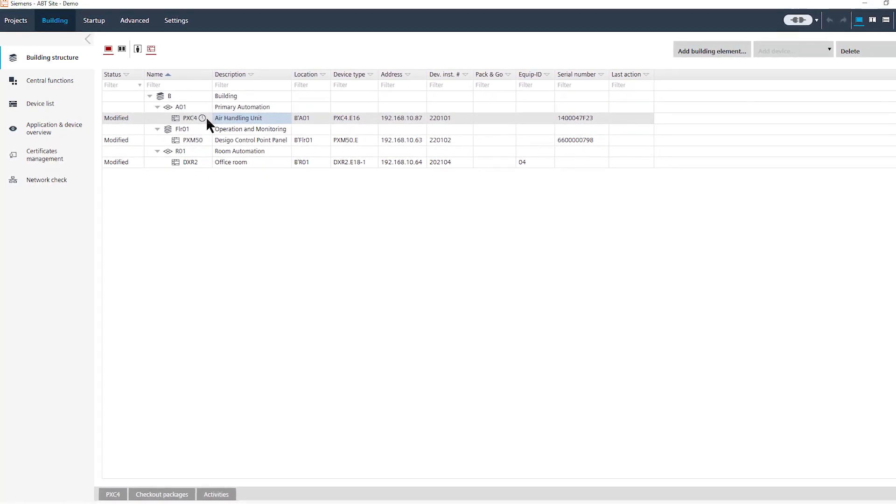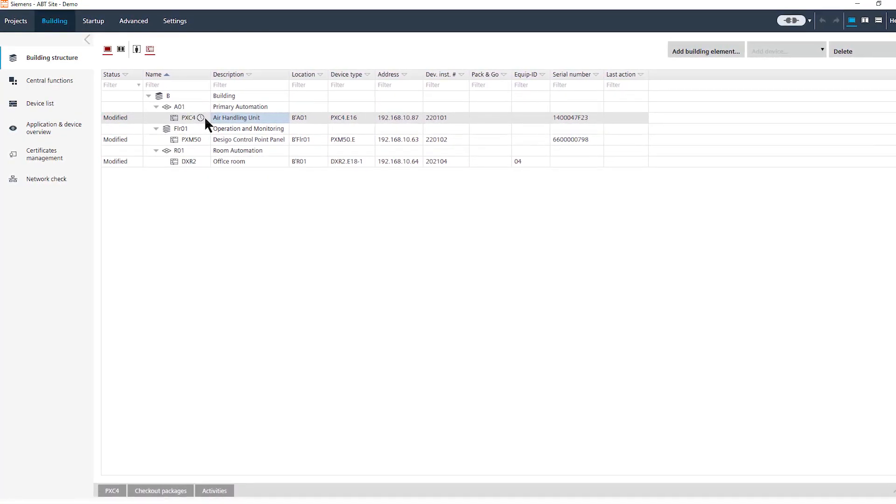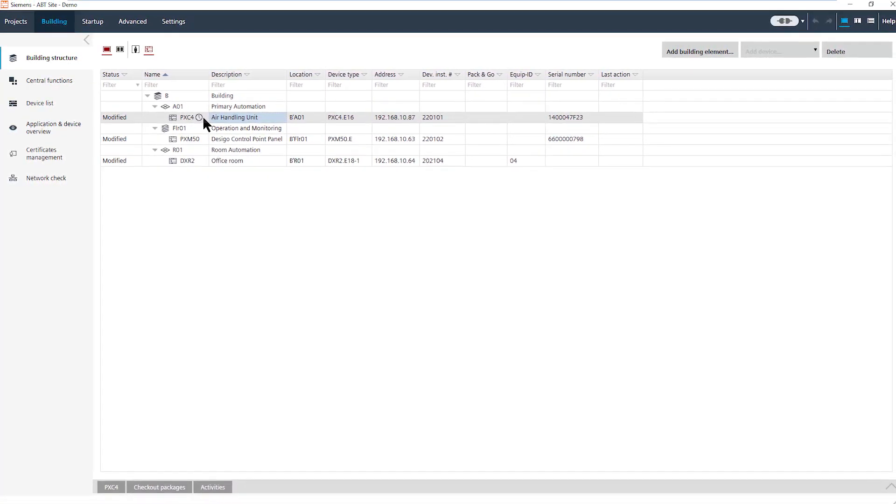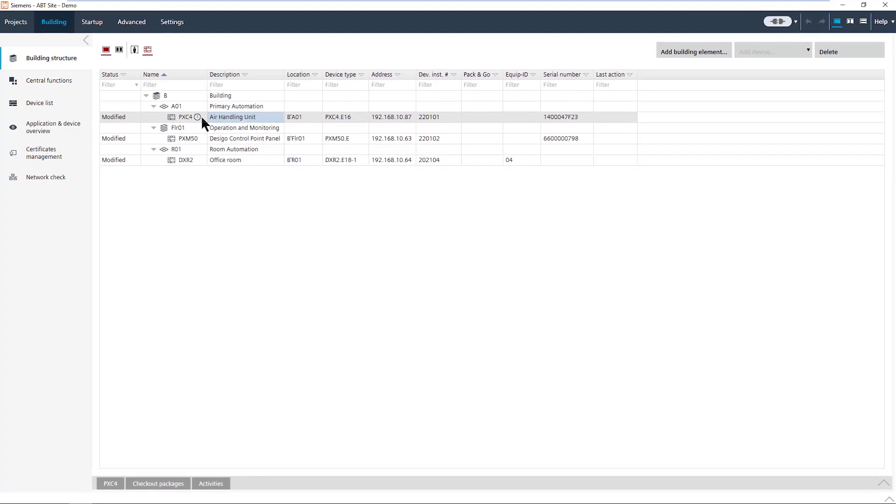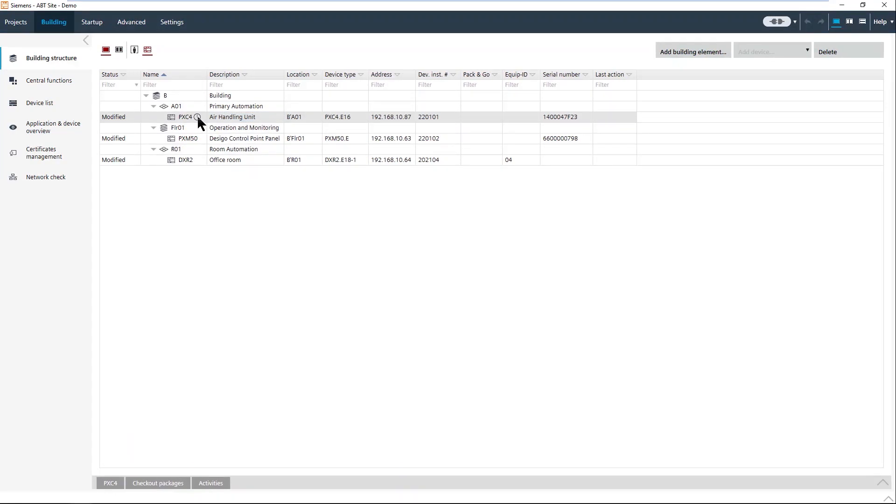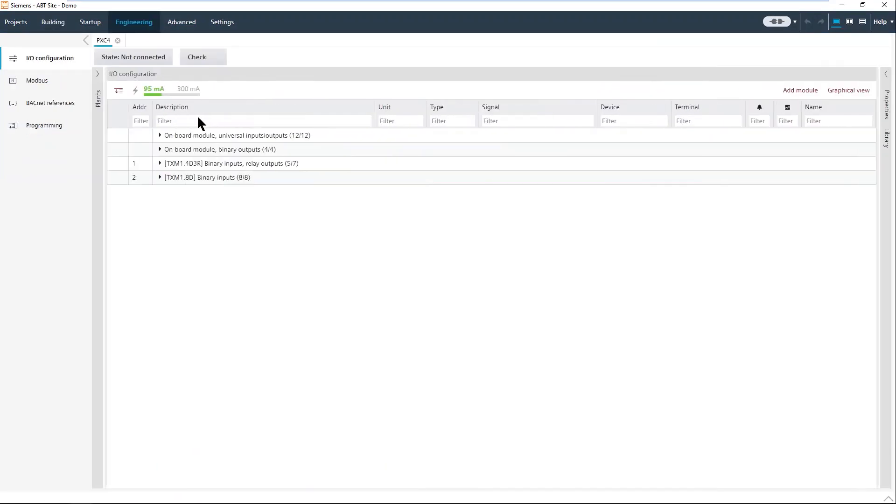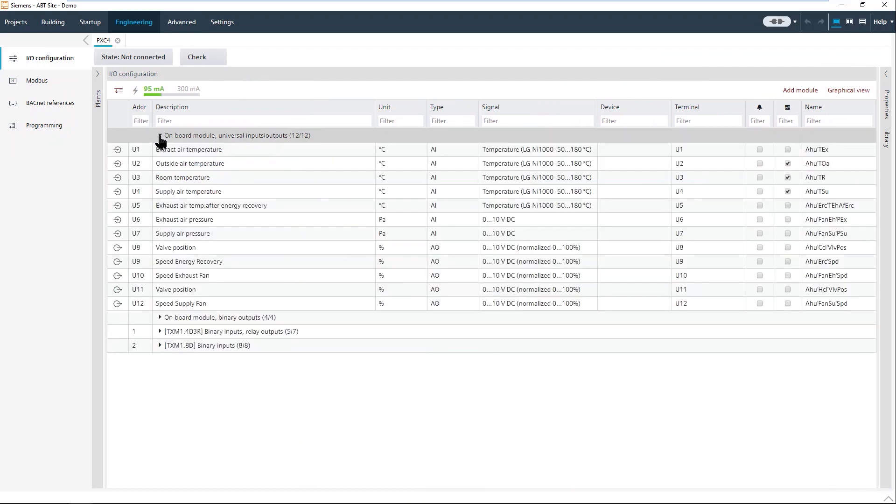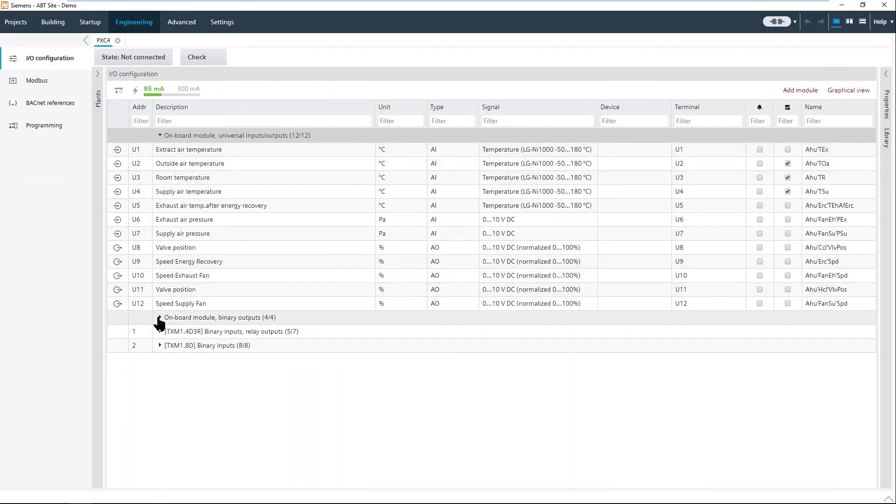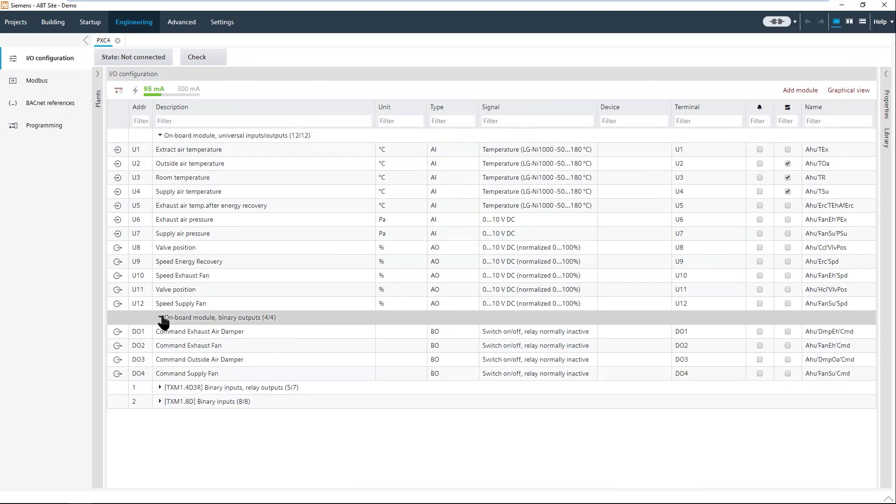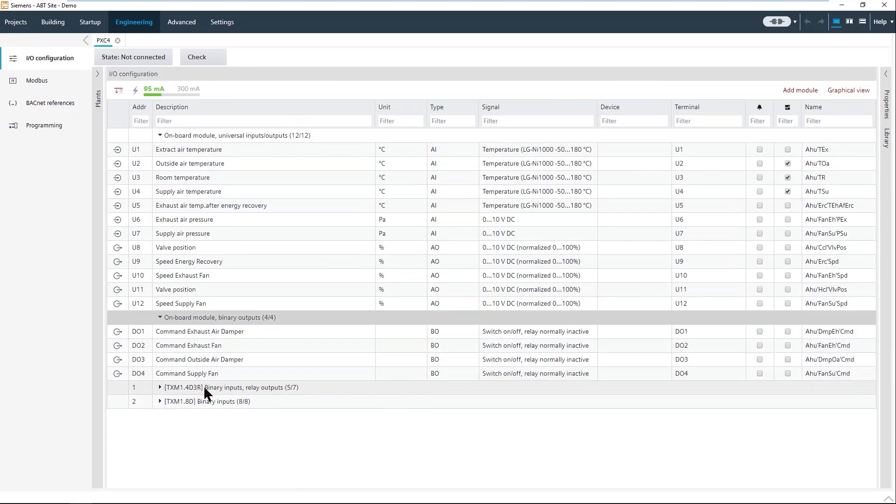Let's go into the air handling unit and look to engineering. In engineering the first step you do is defining the input and output modules you have for the tool. We have here in the PX controller on-board modules, twelve universal inputs and outputs and four binary outputs, relay outputs. You can extend with I.O. modules for your need.